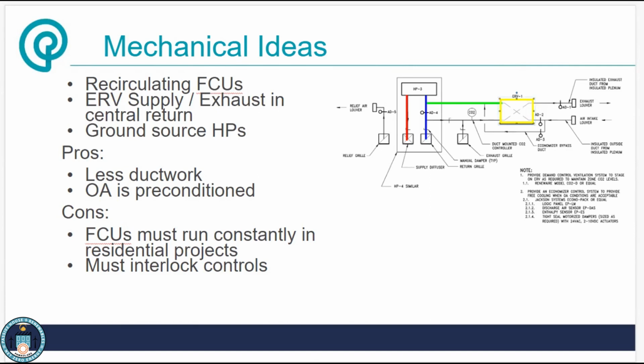This project pulls the supply and the return, pulls the outdoor air and the exhaust air from the return duct of this fan coil unit. This is fairly uncommon and again would only really work well in a non-residential situation where you don't need continuous outdoor air. And it's essentially bringing in one of those packaged rooftop units with the ERV coupled to a heat pump. It's bringing that inside as two separate pieces of equipment.